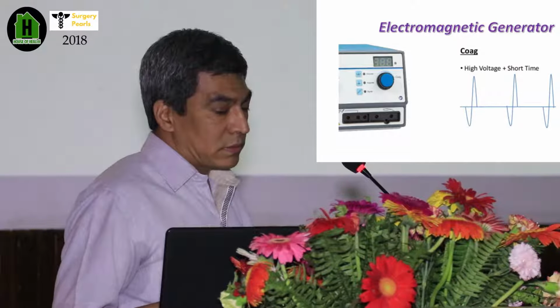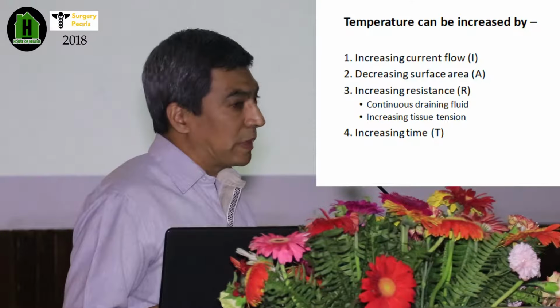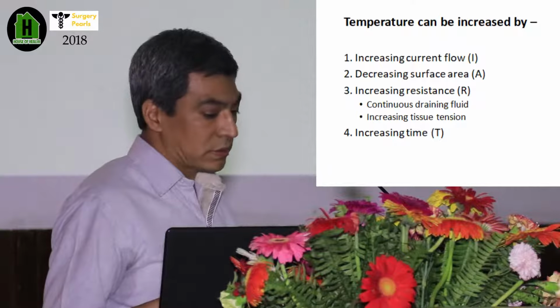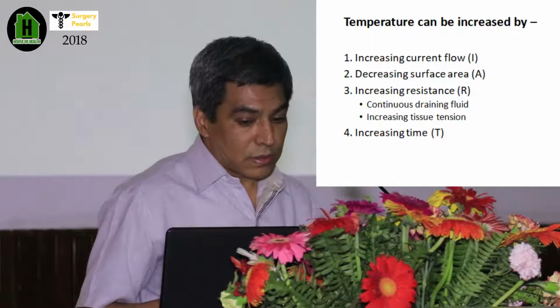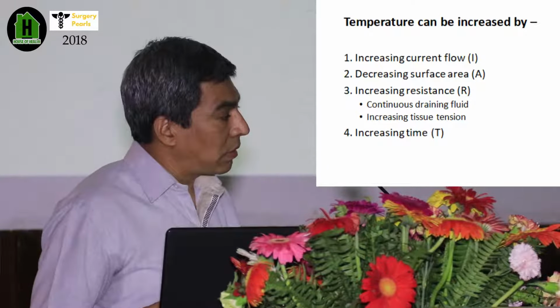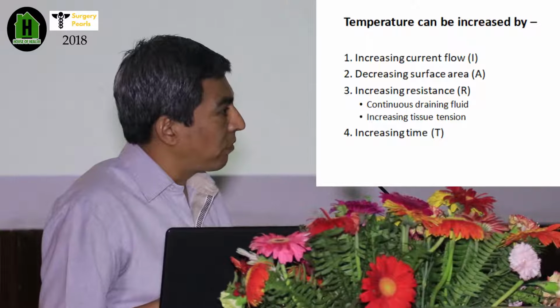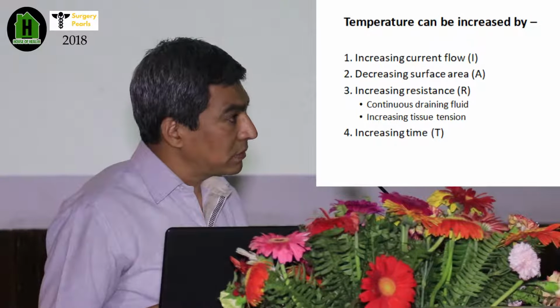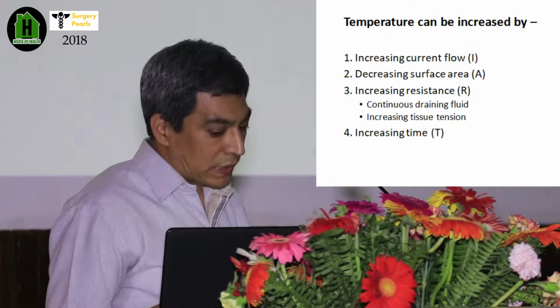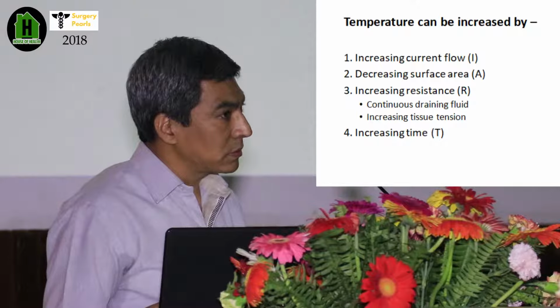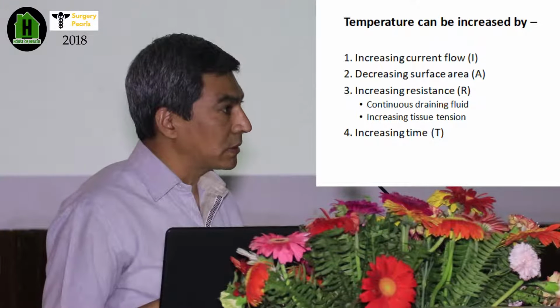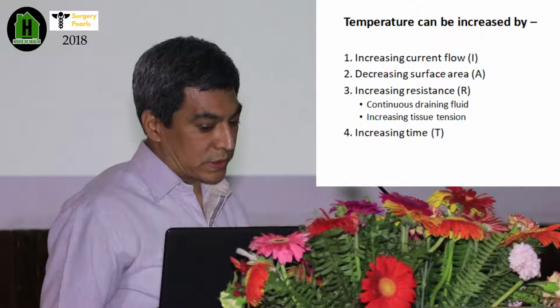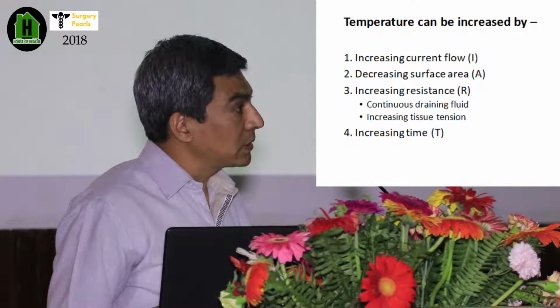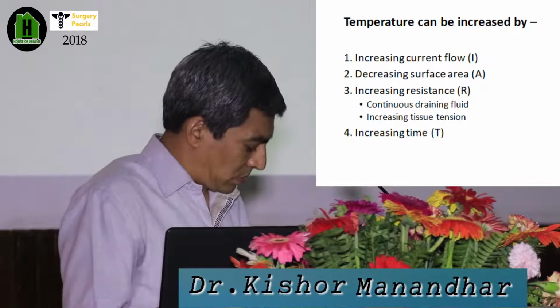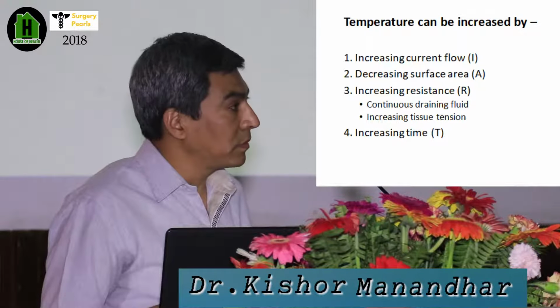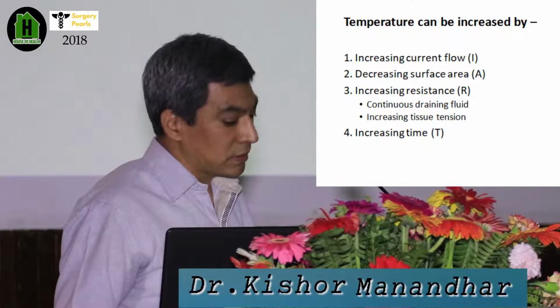Now all the things we are talking about up to now depend on the temperature produced by these devices. So the temperature or the heat can be increased or decreased by altering four different factors. One is you can increase the current of the device to increase the temperature. You can decrease the surface area of the tissues. If the surface area is small, there will be an increase in the resistance, and again the temperature will be high. Or you can increase the temperature by increasing the resistance. Or you can increase the duration. You can increase the duration of application of your cautery. In such conditions, the temperature will be high again.